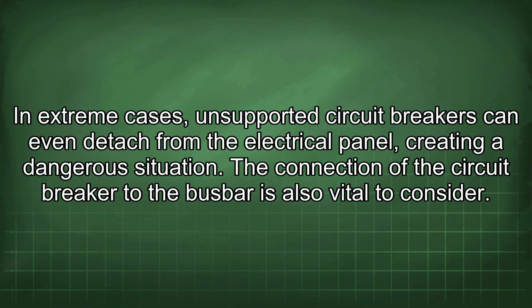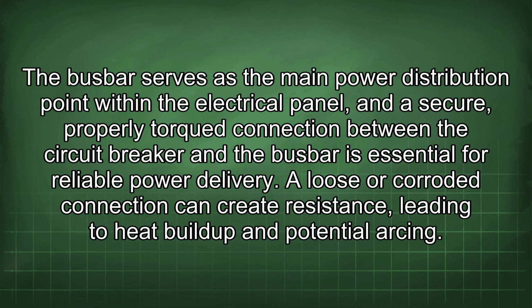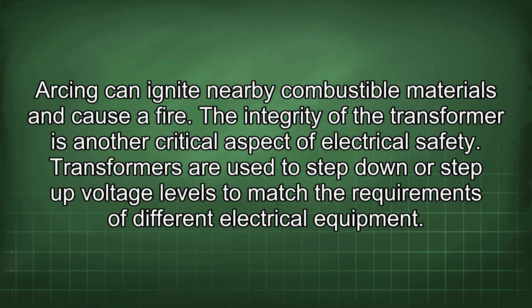The connection of the circuit breaker to the busbar is also vital to consider. The busbar serves as the main power distribution point within the electrical panel, and a secure, properly torqued connection between the circuit breaker and the busbar is essential for reliable power delivery. A loose or corroded connection can create resistance, leading to heat buildup and potential arcing. Arcing can ignite nearby combustible materials and cause a fire.